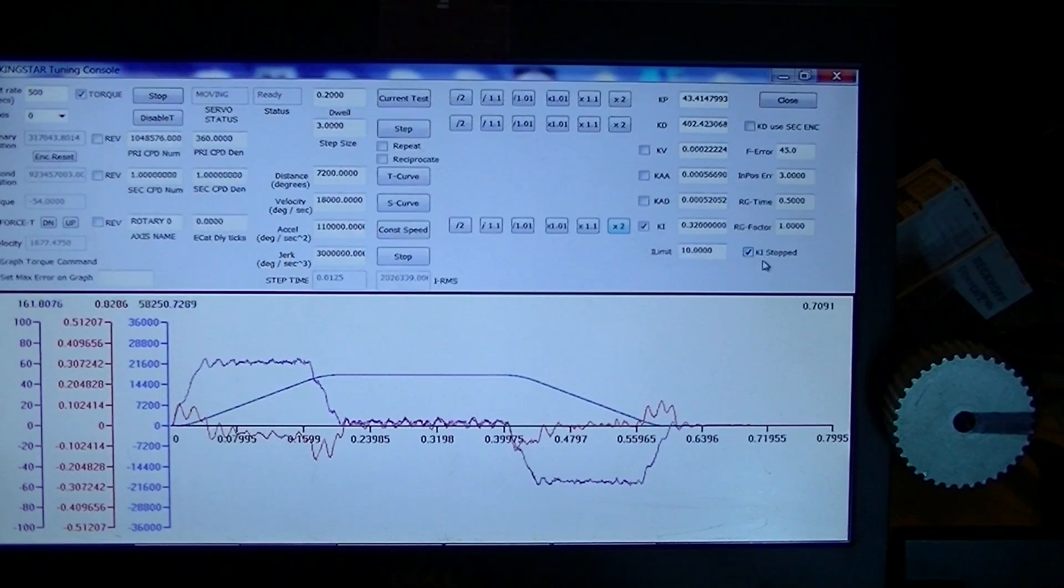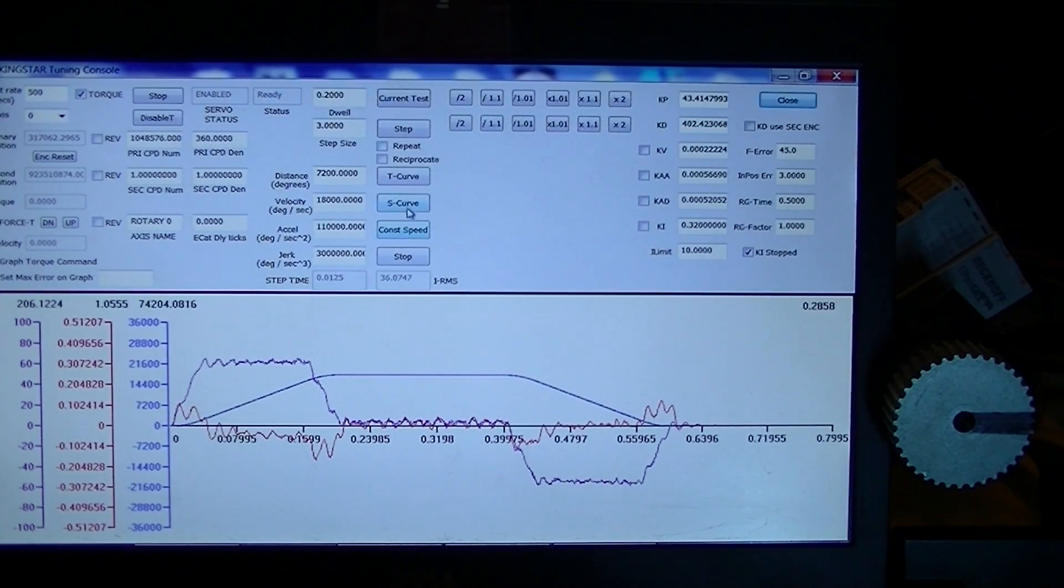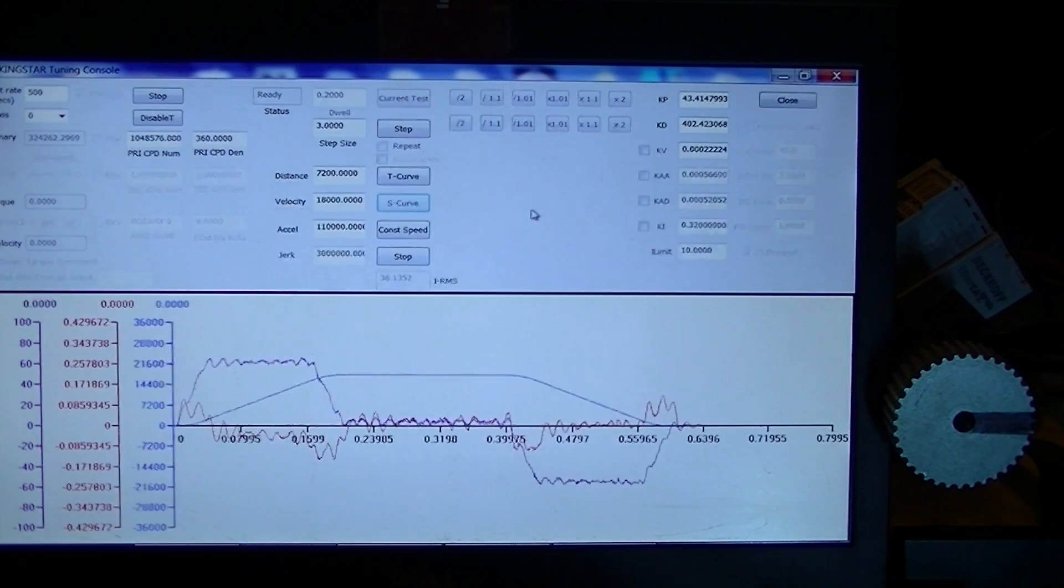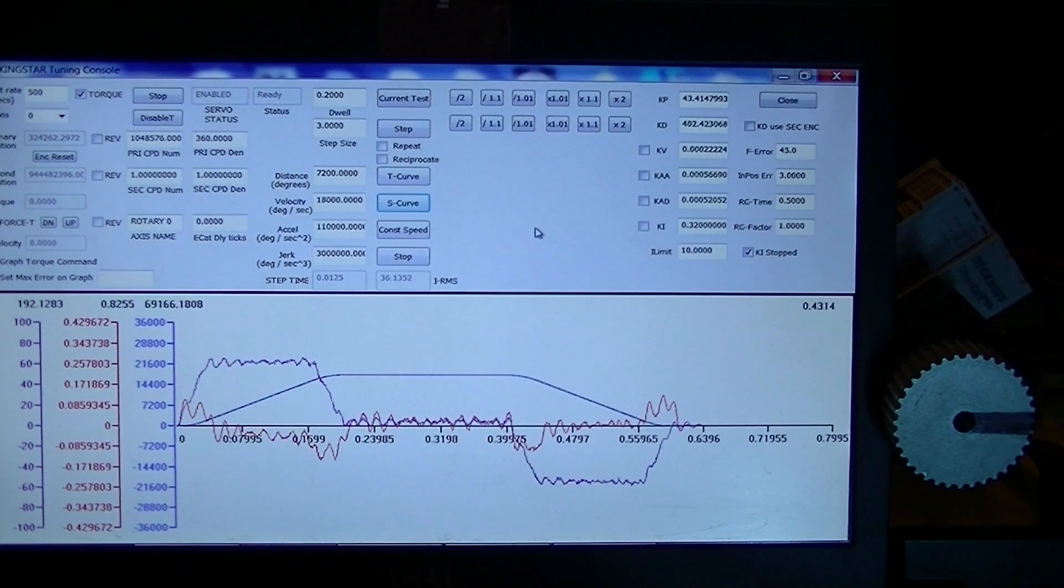So this is the way we prefer to do this. We are now, I can turn this off. We now have a fully tuned PID loop, and we're in good shape. And the very next motor, even if it's a completely different manufacturer, will be able to use this technique. Thank you.